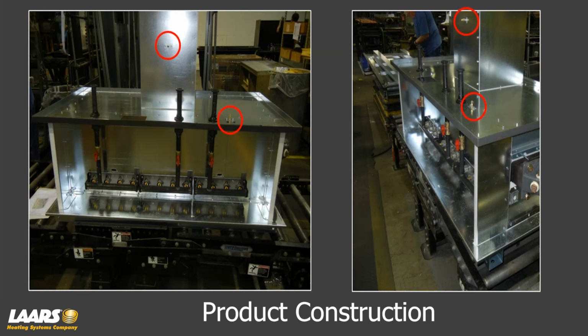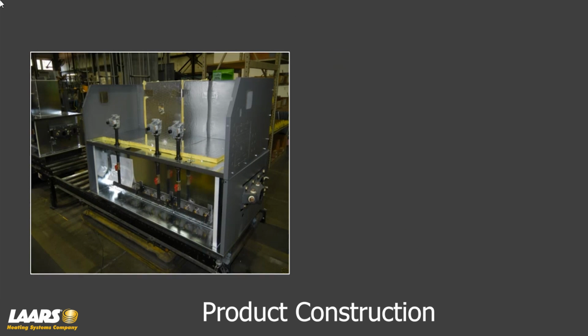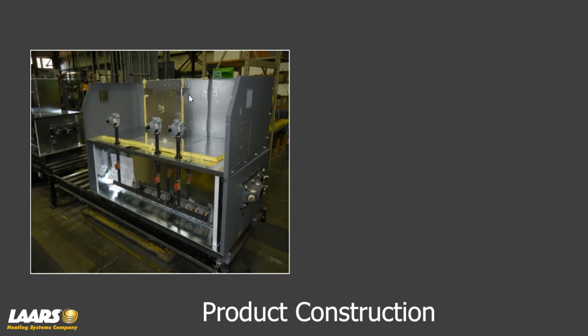Now we also have another barb up here, and that's on your flue collector. Okay? That's for blocked vent. So if you had a blocked vent or a high wind condition, that is a normally closed switch. A high wind condition, I'll use as the example, would open the circuit, shutting the boiler down. Once the wind subsides, that circuit closes again and will refire the boiler or water heater. Next, they'll add the fiberboard insulation over the heat exchanger in the combustion chamber and around the flue collector. Next, they'll start adding the gas valves.